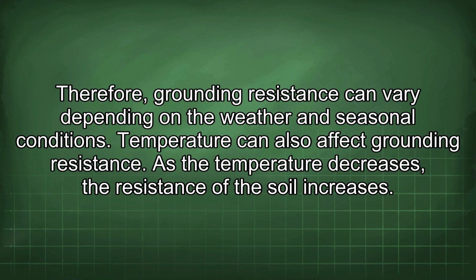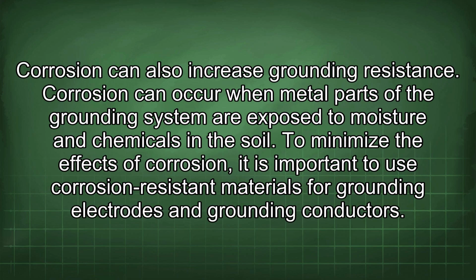Therefore, grounding resistance can vary depending on the weather and seasonal conditions. Temperature can also affect grounding resistance. As the temperature decreases, the resistance of the soil increases. Corrosion can also increase grounding resistance. Corrosion can occur when metal parts of the grounding system are exposed to moisture and chemicals in the soil.